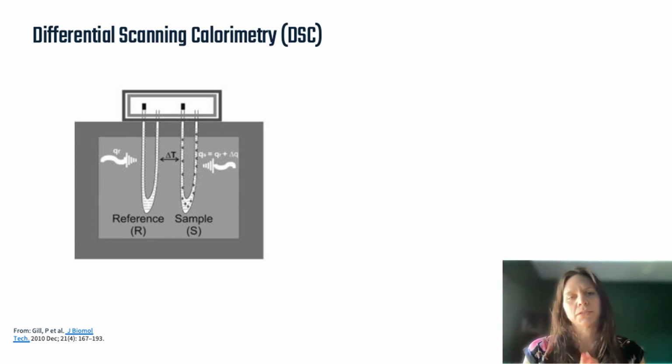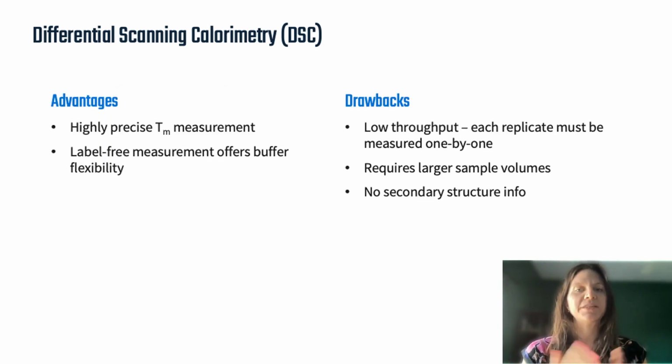So DSC is considered the standard for TM measurements, not just because it's been around for so long, but because it works in so many different fields. Polymer chemists, liquid crystal researchers, and chemical analysts all use DSC to do their work. DSC instruments are designed to be highly sensitive, and many function at a wide range of temperatures.